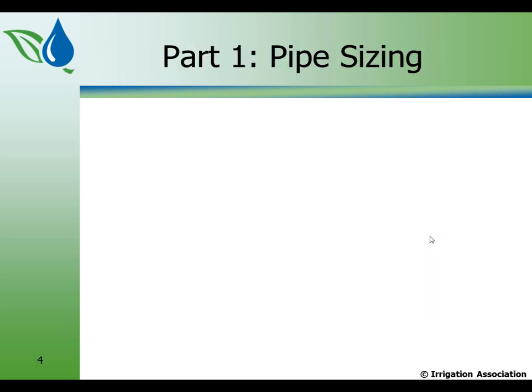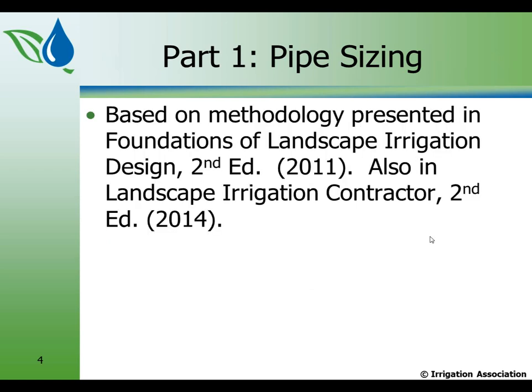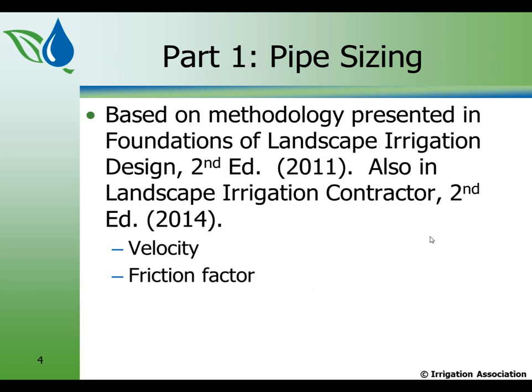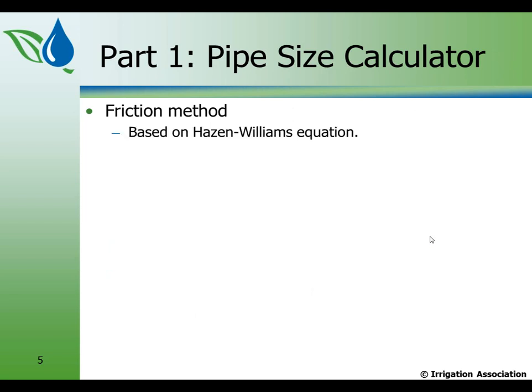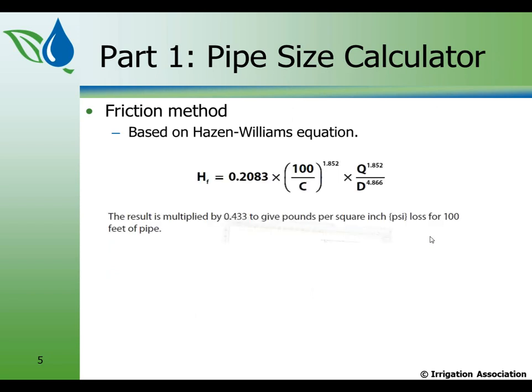So let's launch off here on the pipe sizing part. The pipe sizing is based on methodology that's presented in Foundations of Landscape Irrigation Design Second Edition. It's also in Landscape Irrigation Contractors Second Edition. And in those manuals, we talk about the velocity method, the friction factor method, and how to utilize those and when to utilize them. So in the friction method, following the methodology that's in Foundations of Landscape Irrigation Design, it is based on the Hazen-Williams equation. Now I'm going to show you the Hazen-Williams equation, and then I'm going to tell you that really, you don't have to worry about that. It's built into the software.